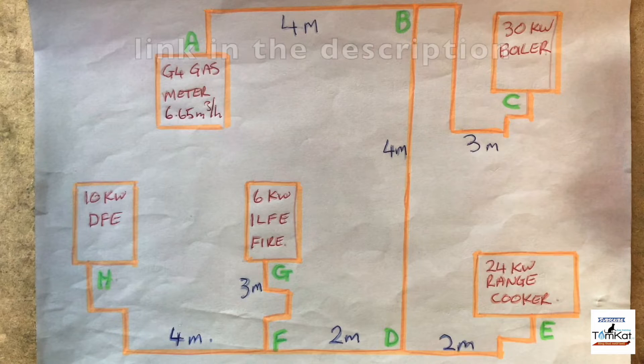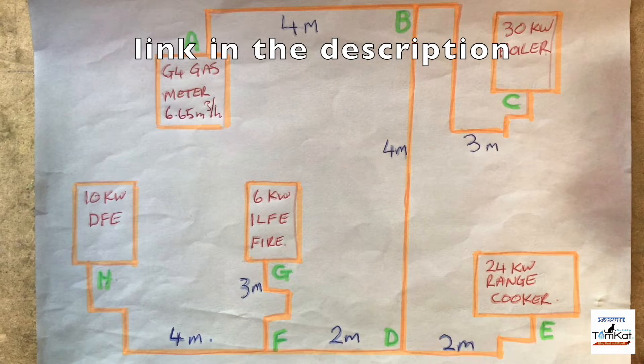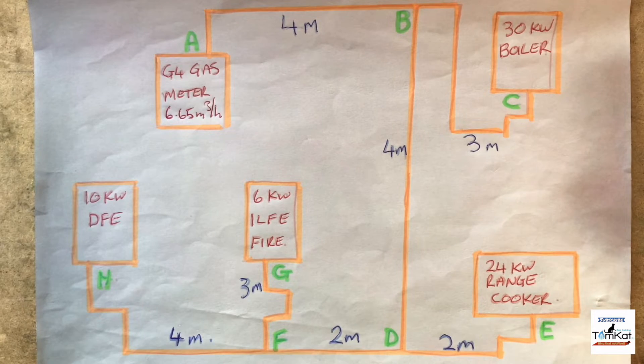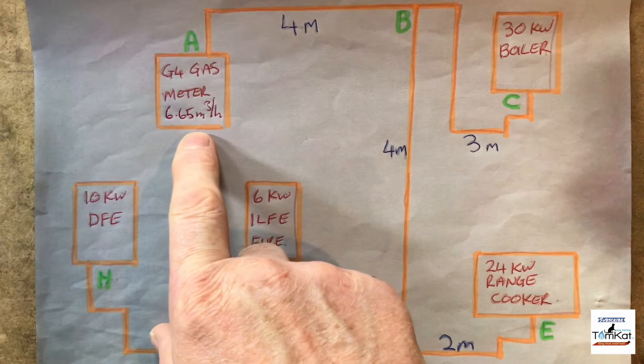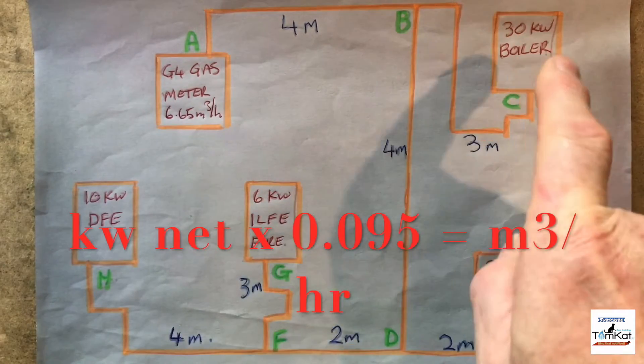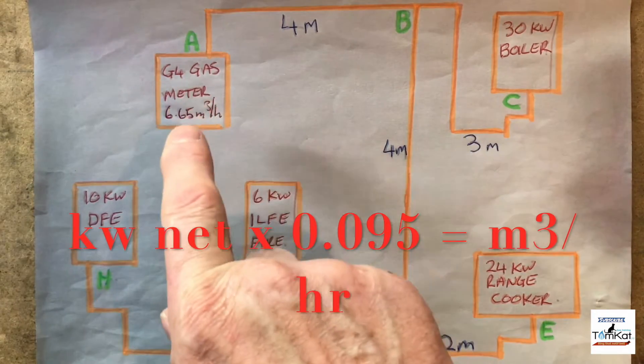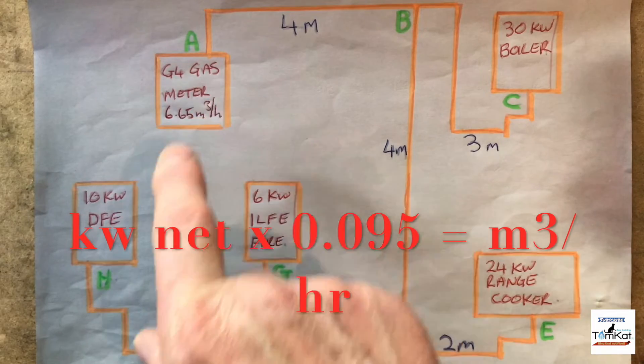Let's find out exactly what the diversity factor is and how we size a gas meter correctly. You might recognise this drawing from our pipe sizing video — if you haven't seen it, go have a look. When we did the pipe sizing we had a G4 meter giving us six meters cubed per hour, but our total load for the boiler, cooker, and two fires comes to 6.65 meters cubed per hour.